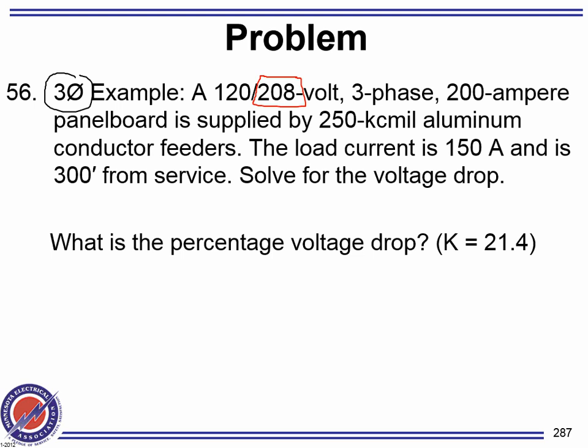The conductor is 250 aluminum. The load, okay, there are two amps. Here's the confusion. There's a load amp and a panel size. Which would you use? Would you use the panel size or the load amp? Always by load. So don't get confused by the two amps here. Which amp are you going to use? The load. You're after the load.